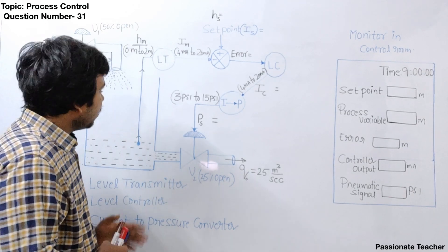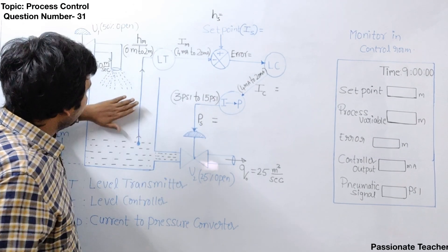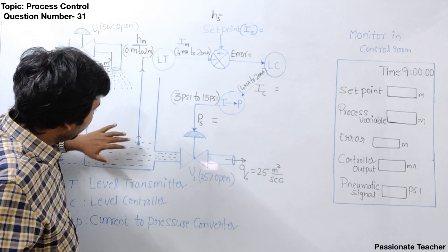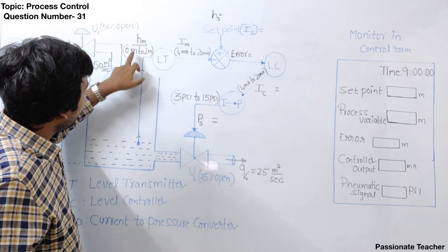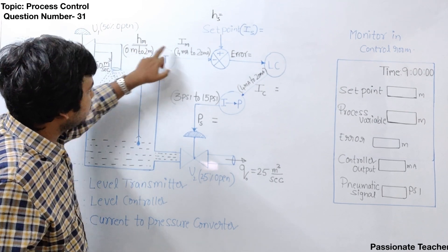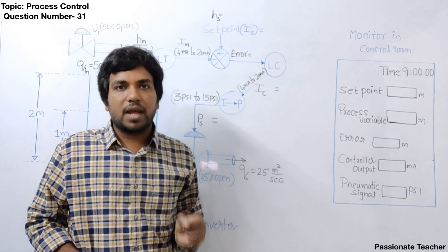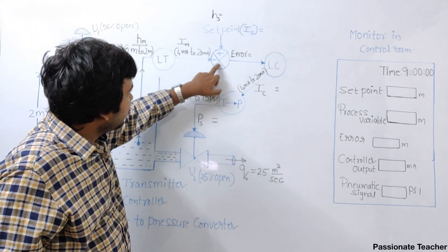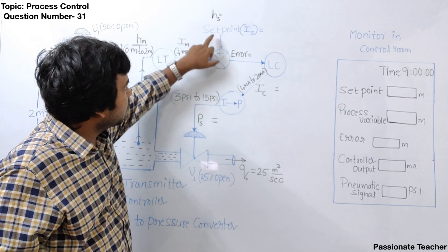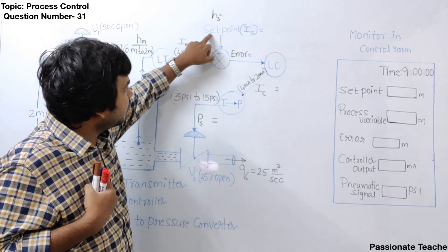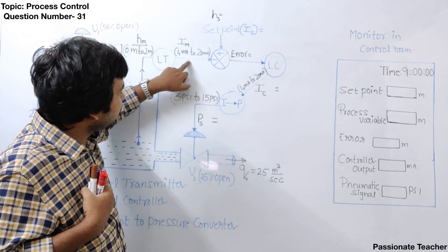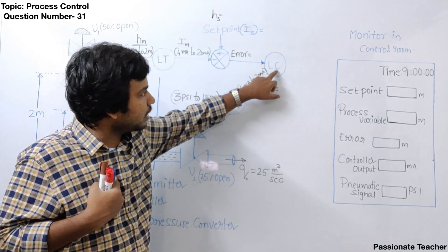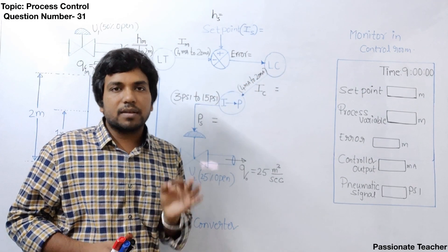Now looking at the overall figure, there is a device called a level transmitter. This level transmitter measures the water level inside the tank and converts it into current, because current is a very standard signal used in process instrumentation. This current goes to the error detector, which receives the desired input. The difference between the desired input and the measured value is subtracted by the error detector, and the error is given to the level controller (LC).